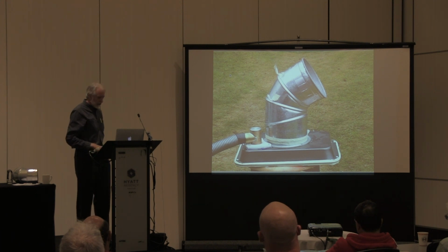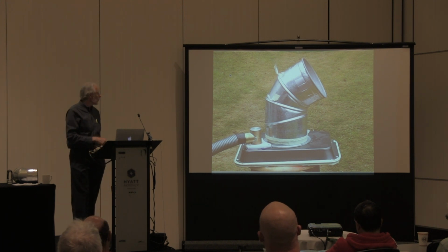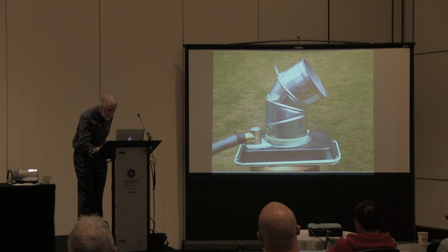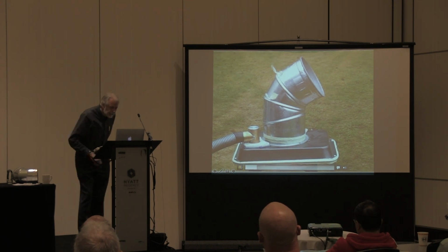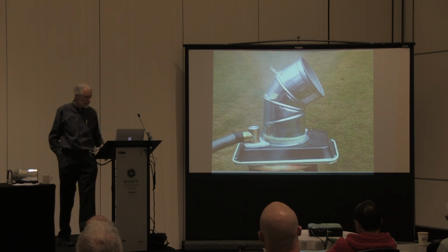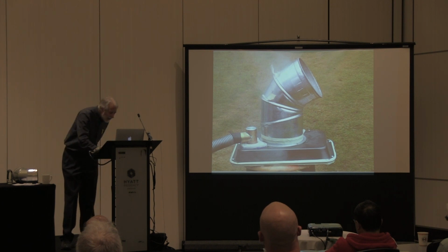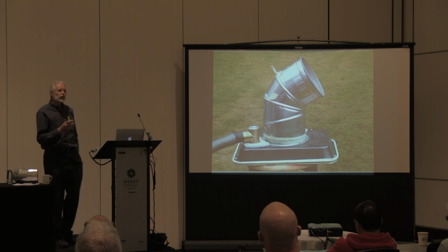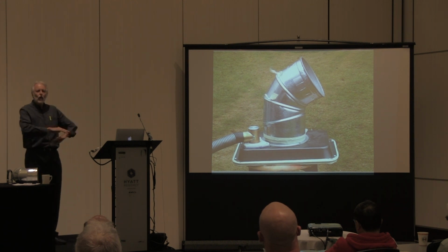Now, if I don't screw this up, this should work. But what I'd like to do is show you what happens when you put a smoke generator on this here elbow. It's 8 seconds. What we learned in this game is that once you have leaky ductwork, you can fill up a whole house with smoke.